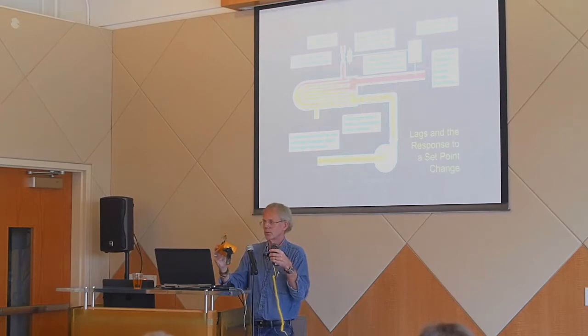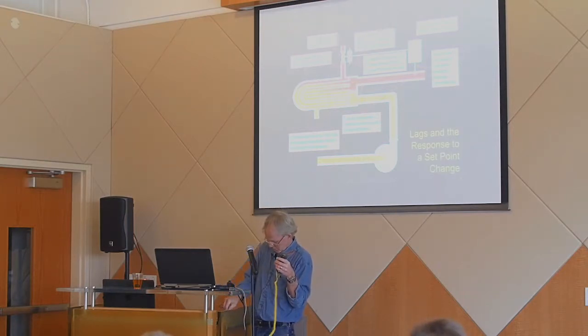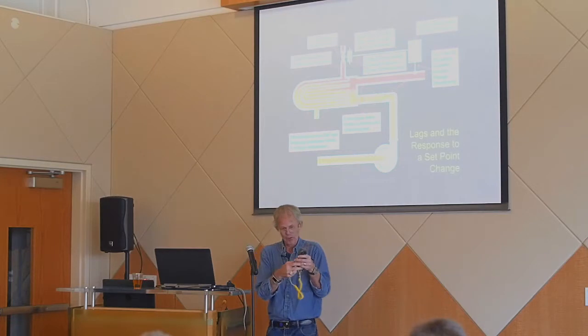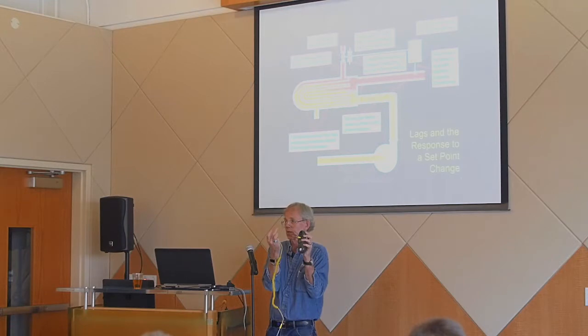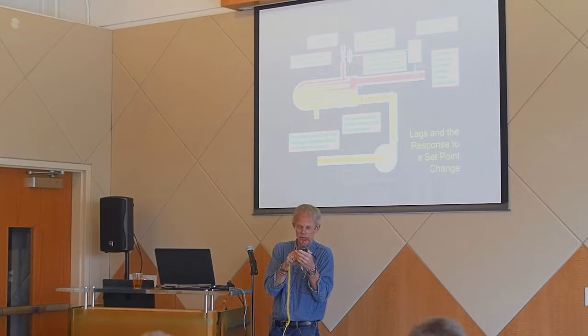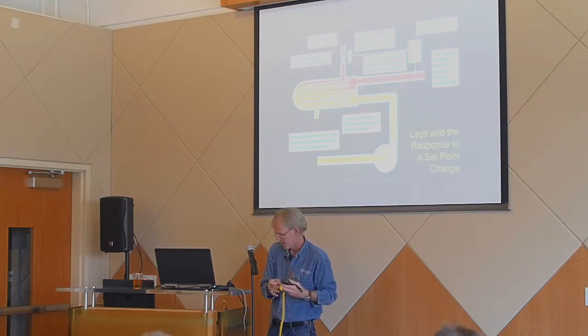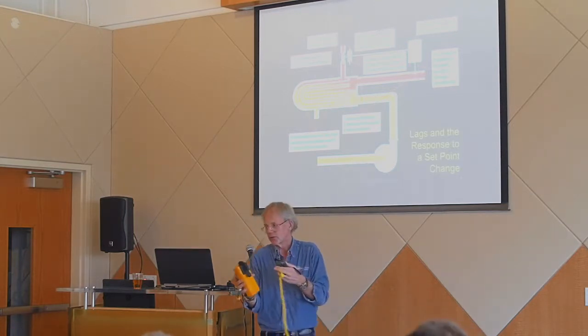So you can do a little experiment when I pass these around. Just blow on it and watch how fast the little bead reacts compared to how fast the sheath reacts. This just plugs in. You just have to watch polarity. There's a plus. If you look close, there's a plus on the thermocouple. There's a plus on here. Just get the pluses lined up. I'll turn it on here and set it to degrees Fahrenheit. And so you can, if you want, you're under no obligation to do this, but do a science experiment.